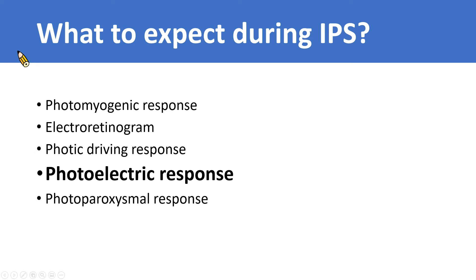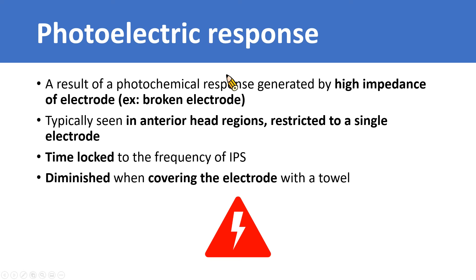Let's move on to photoelectric response. Photoelectric response is a result of a photochemical response generated by high impedance of an electrode, such as when an electrode is broken. Like other responses during IPS, photoelectric response is typically seen in anterior head regions and is restricted to a single electrode, especially the broken one. It also has a time locked feature relative to the frequency of IPS, and diminishes when covering the electrode with a towel.